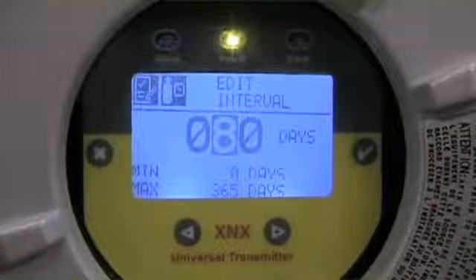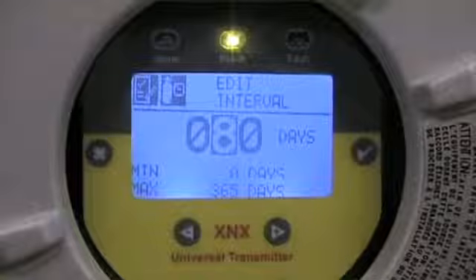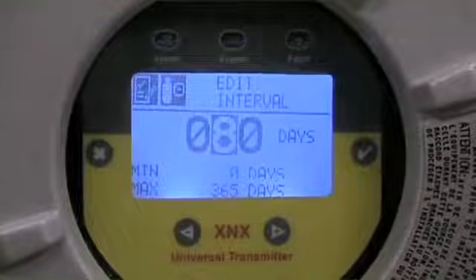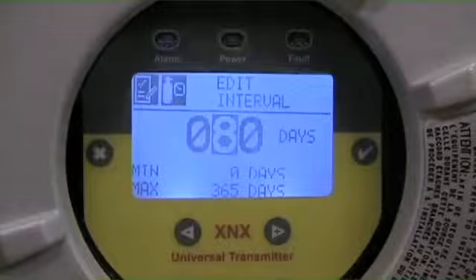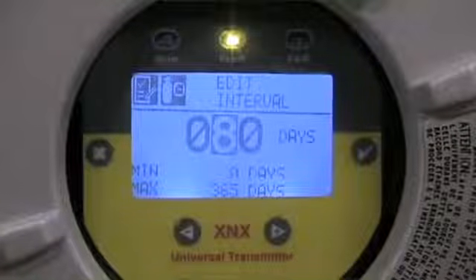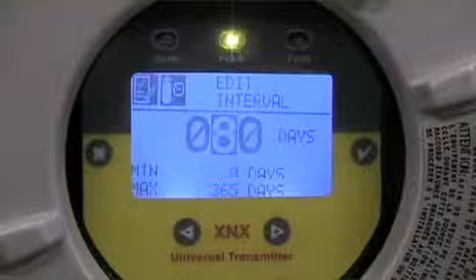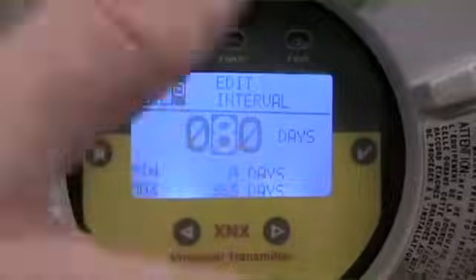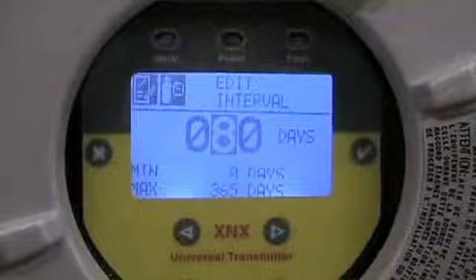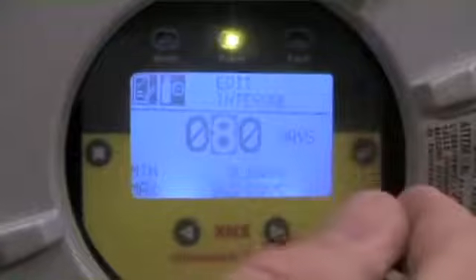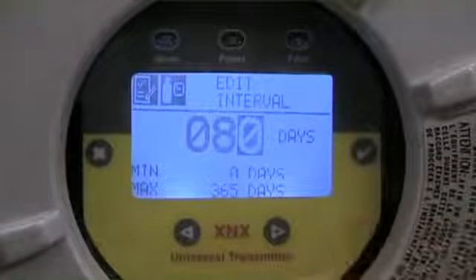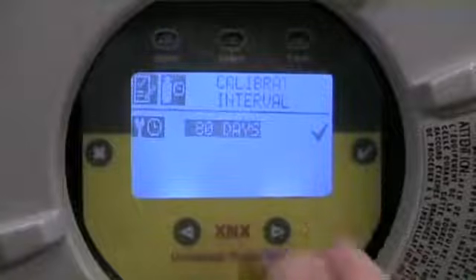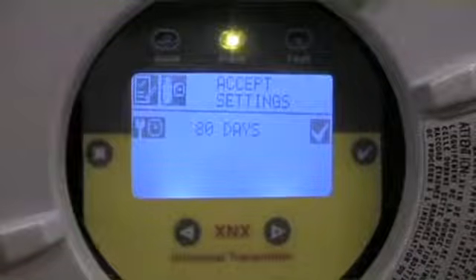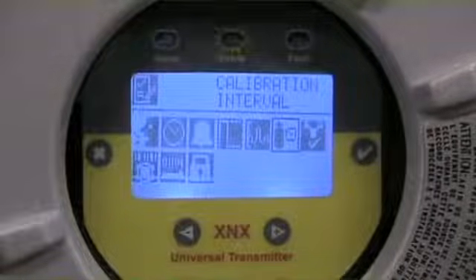You can see what's available is you can set 0, which turns off that cal reminder, or the maximum that would be allowable is 365 days. The sensor simply will not allow you to operate past that period of time without having a calibration event. But again, you can set whatever your safety policy is and make that an automated reminder that calibration needs to be accomplished according to your policies. When that's accepted, your option here again is always to move over. You can either accept, so it will now change it to the new value, or if we don't accept and we back out, we go back to whatever our default function is.